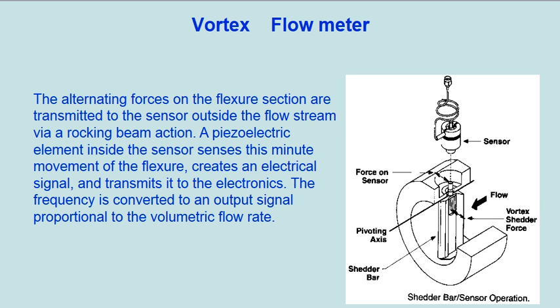The alternating forces on the flexure section are transmitted to the sensor outside the flow stream via a rocking beam action. A piezoelectric element inside the sensor senses this minute movement of the flexure, creates an electrical signal, and transmits it to the electronics. The frequency is converted to an output signal proportional to the volumetric flow rate.